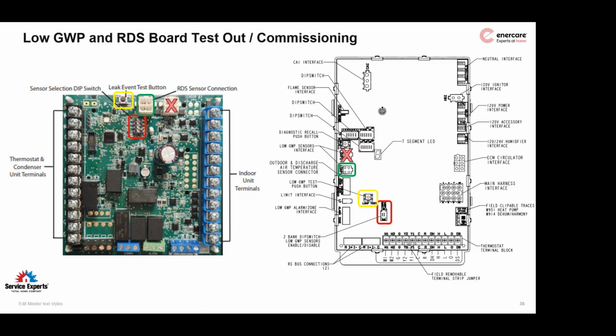Confirm that they stop, and simply push that test button again to come out of that test function. Those are the two tests to commission to make sure that that system is working appropriately. And then again, God forbid there's ever a refrigerant leak with the A2Ls, in this case R454B, the leak mitigation procedures will function. It'll dissipate any potential leak around the house to keep it way, way, way below its lower flammability limits.